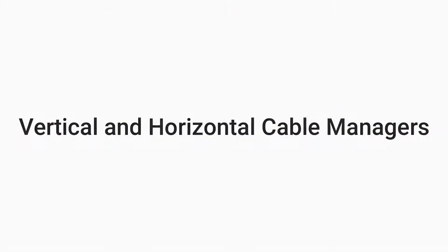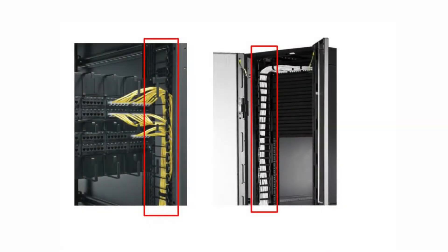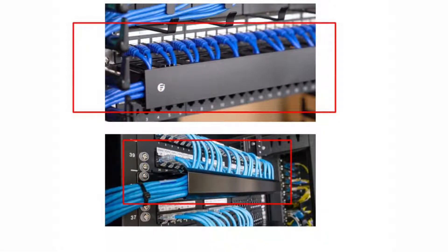While ladder racks manage the cables above the servers, inside the server rack or cabinet there are additional cable managers that organize the patch cables. Vertical cable managers are on the outside edges of the rack and manage cables running up and down. Horizontal cable managers are mounted to the rack between server devices and keep cables connected to the servers, directing them through a tunnel to the vertical cable managers along the side.